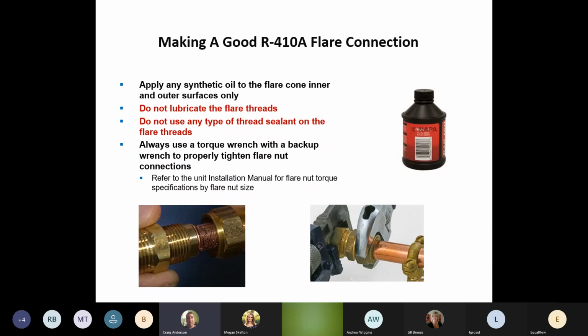When we're doing our flare, sometimes your nut is a little tight. Just take some synthetic oil, put it on your copper pipe, and help free up your flare nut so that when you're putting it on, you're not jamming or cross threading. Try not to get it on the threads because we don't want any oil on the threads. We want it to be brass to brass. Once that brass to brass is connected and we have a good flare, chances are you're not going to have a leak.